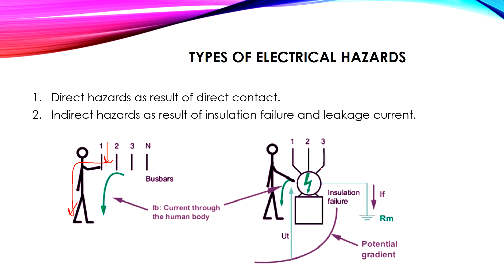The second type is indirect hazards. For example, if we have an electric motor supplied by three-phase power in a delta connection, the motor enclosure normally carries no current. However, in the case of insulation failure — say on phase two — a small leakage current passes through the enclosure. When a human touches the surface, current flows through them to the ground. This is called an indirect hazard, because it results from insulation failure and leakage current.